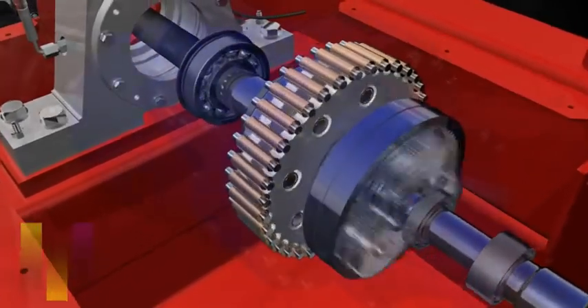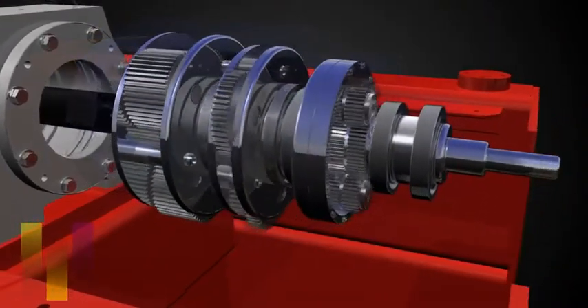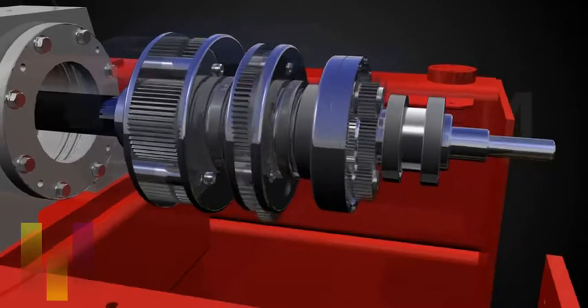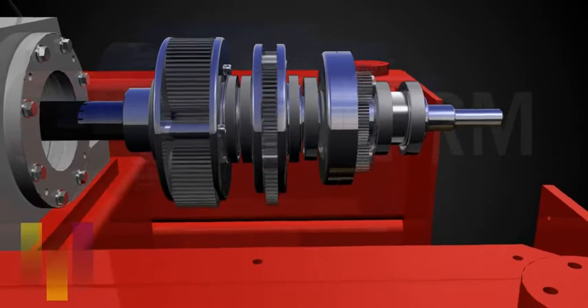If a gearbox is used, it is always an indirect drive system due to the fact that the centrifuge conveyor shaft is not directly driven by the motor, but rather the sun shaft of the gearbox is driven and controlled via a VFD.